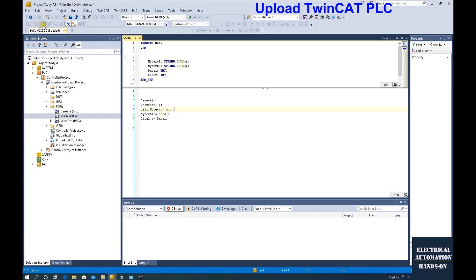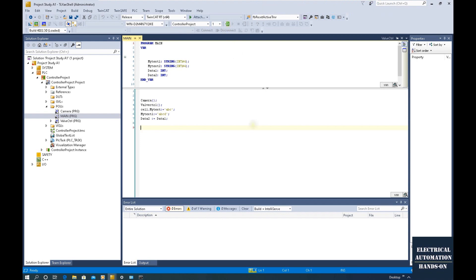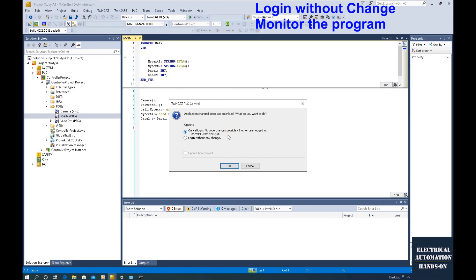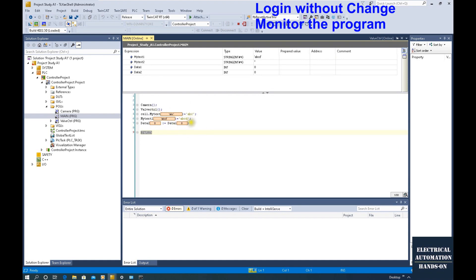My remote controller is running inside one laptop PC. It will show a login prompt — we can cancel the login. But in most cases when we try to upload this project, we need to online monitor the current program. So most of the time we will select 'Login Without Any Change'. Using this way, we will not download any change to the remote PLC — we just need to monitor online using this uploaded project. So if I hit 'Login Without Any Change', we can see the current status of this remote PLC controller.